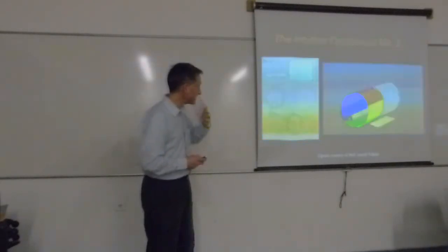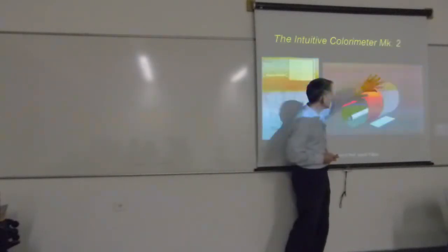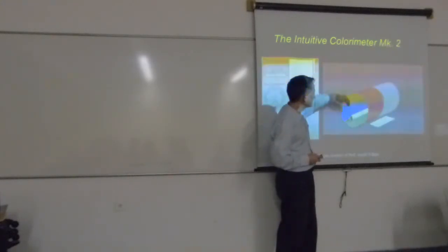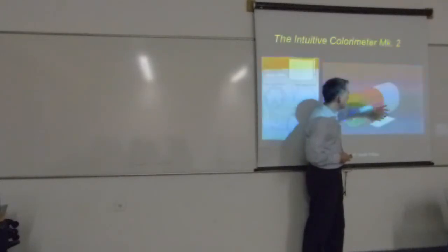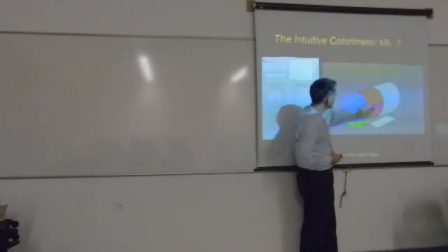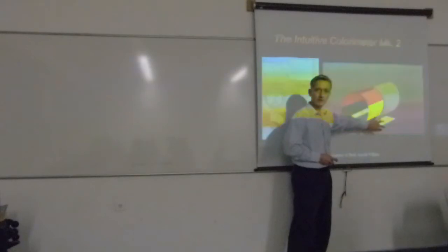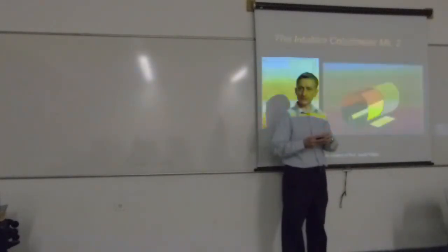So the colorimeter we have here in Hadassah is a Mark II colorimeter. If you're interested in how it works, the way it works is you have a fluorescent tube inside the instrument, which is a special tube designed to be daylight type of tube. That tube is inside a cylinder, and that cylinder is divided into two halves. A half that has coloured filters, and a half that has grey. And what happens is the light from the fluorescent light shines through a window inside the instrument, and this is then scattered, the light that comes through.